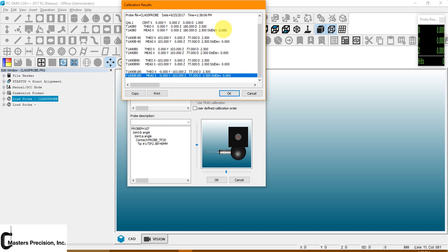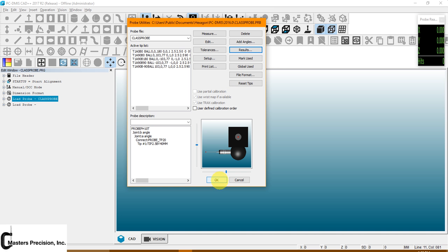Check your probes, make sure there's no damage, clean it, make sure you got the right tip diameter in. Anything over 10 thou, you've got an issue. You need to stop what you're doing, start looking back over all the mentioned items. Is your tip damaged? Is your shank bent? Do you have contamination on the sphere or your probe stylus itself? Once you're done, if you're happy with this, you hit OK. Go back down and hit OK again, and this will save the calibration results to this file named class probe, or whatever you have it named as.